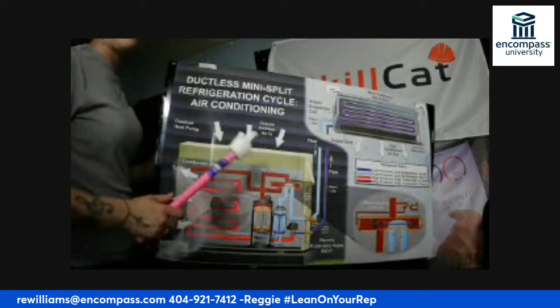So in a mini split situation, here's our indoor unit. Here's our evaporator coil. So when we're entering into the evaporator coil, we're entering as a low pressure, low temperature vapor. So again, we're in vapor form, but we're not high pressure and high heat. And that's a common misconception. A lot of people think that we can only be in vapor form if we're high pressure, high heat. Not the case with the refrigeration cycle.